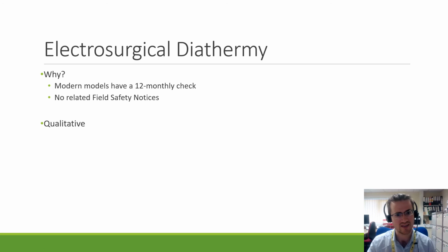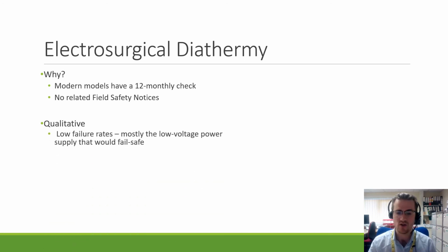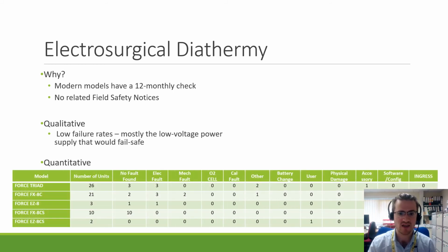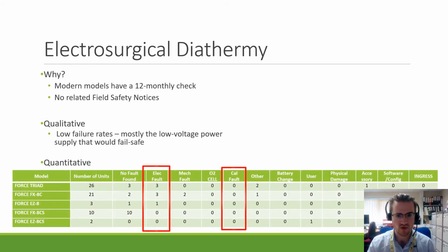Looking at the qualitative data, there were very low failure rates, which were mostly low voltage power supplies, and they would fail safe. So there's reassurance that the devices just wouldn't turn on when they failed. Quantitative data, again, the checks were looking at electrical and calibration faults, of which you can see there's a very low number of faults, and these would be part of our surveillance data.